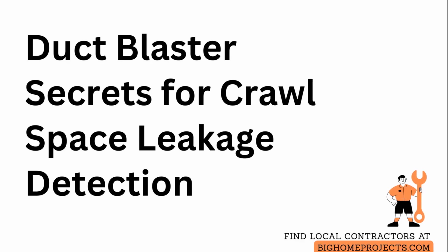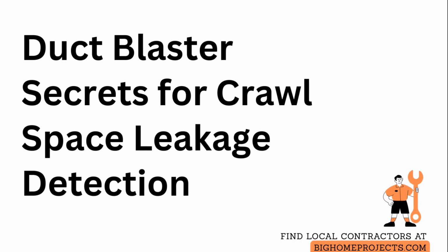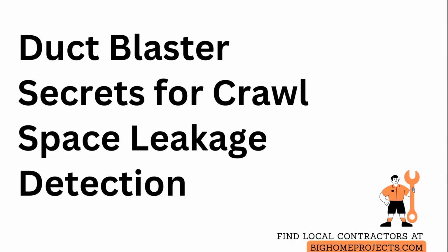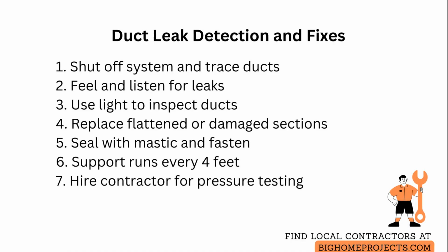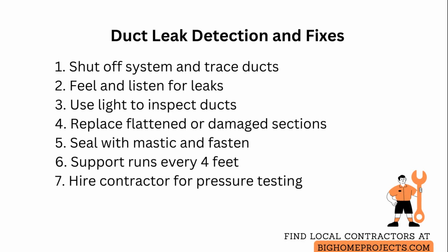What could cause airflow into a crawl space or odd areas is usually duct system integrity failures that allow conditioned air to escape where it is not needed. Poorly installed or damaged ducts often have disconnected sections, open joints, or crushed runs that leak large volumes of conditioned air into crawl spaces or other voids.